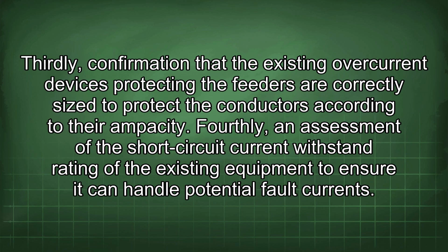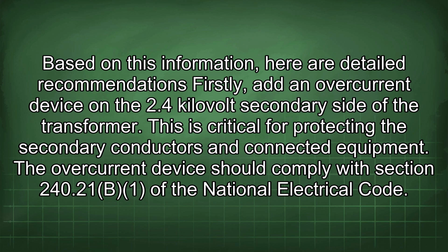Thirdly, confirmation that the existing overcurrent devices protecting the feeders are correctly sized to protect the conductors according to their ampacity. Fourthly, an assessment of the short-circuit current withstand rating of the existing equipment to ensure it can handle potential fault currents. Based on this information, here are detailed recommendations. Firstly, add an overcurrent device in the 2.4 kV secondary side of the transformer. This is critical for protecting the secondary conductors and connected equipment. The overcurrent device should comply with Section 240.21(B) of the National Electrical Code.